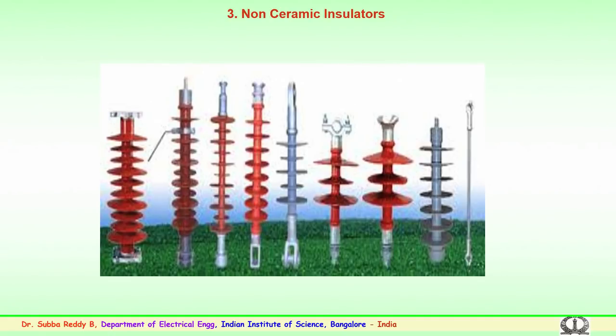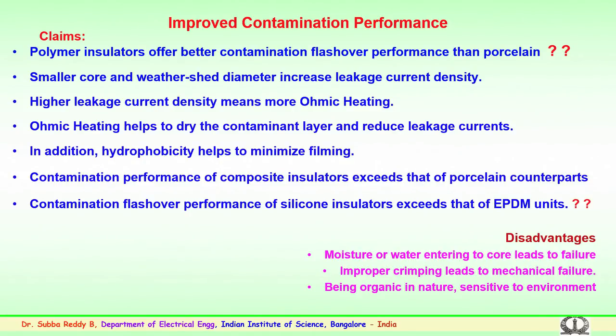So, polymer or composite insulators have some better advantages compared to porcelain or glass. We will look into the advantages of these insulators. Polymeric or composite insulators offer better contamination flashover performance than porcelain insulators. This is one of the important properties, where the utilities are much more comfortable using this insulator in polluted or contaminated conditions and in zones where contamination or pollution flashover regularly occurs.